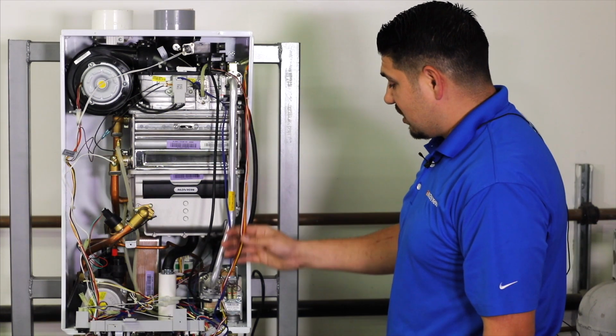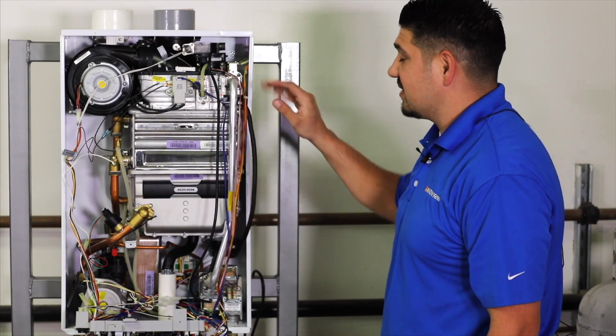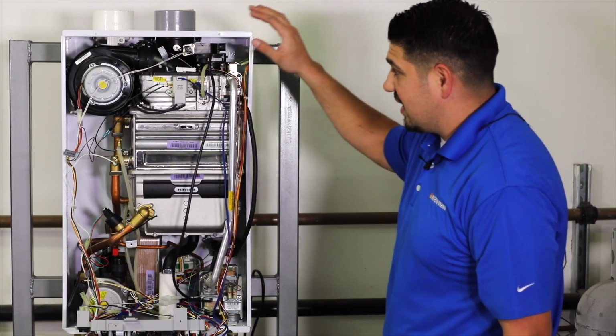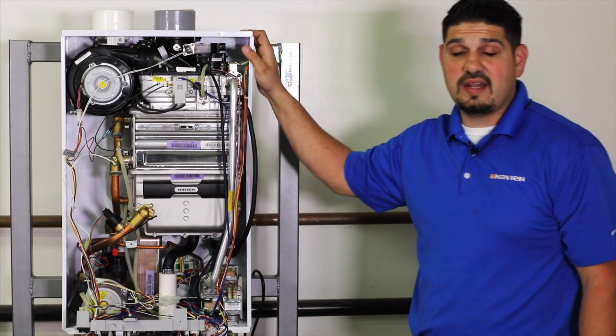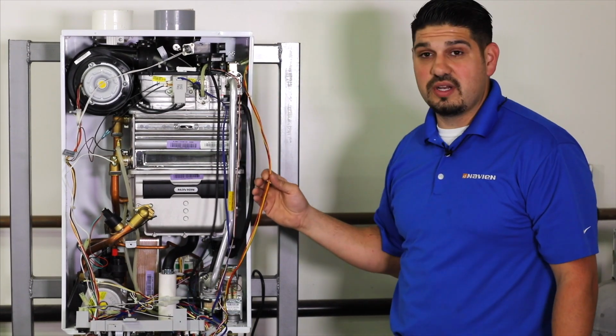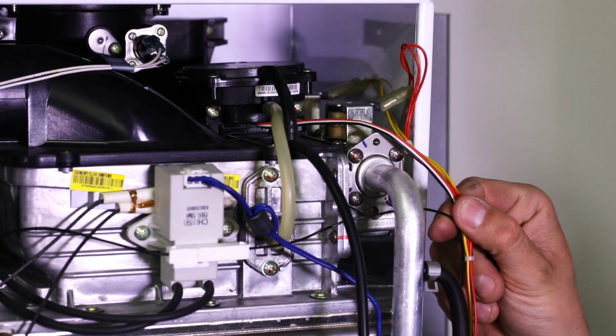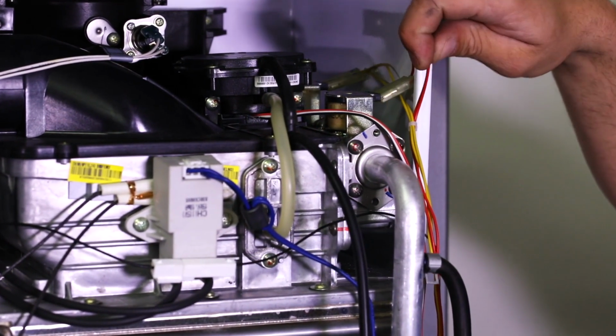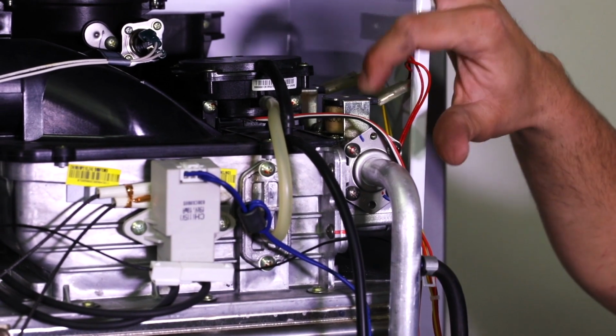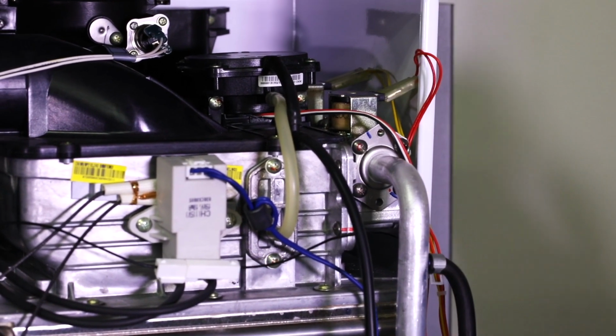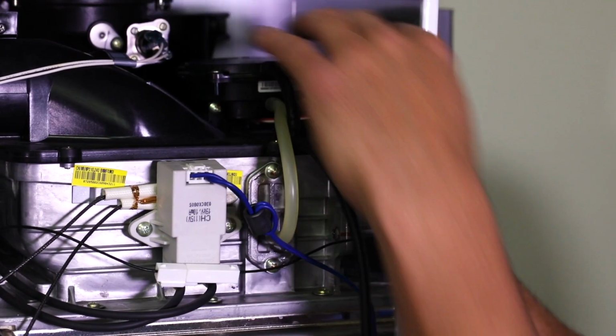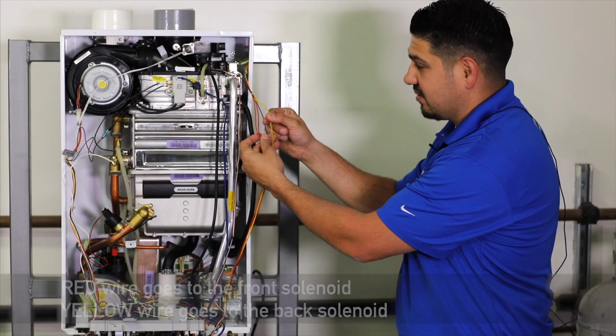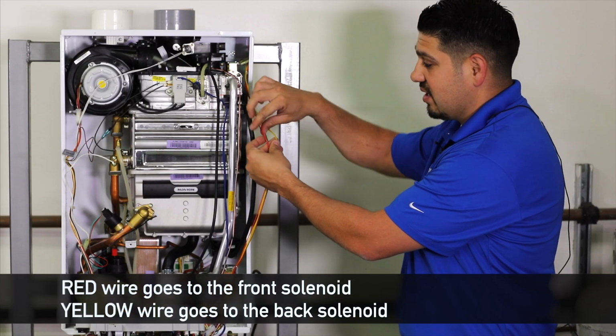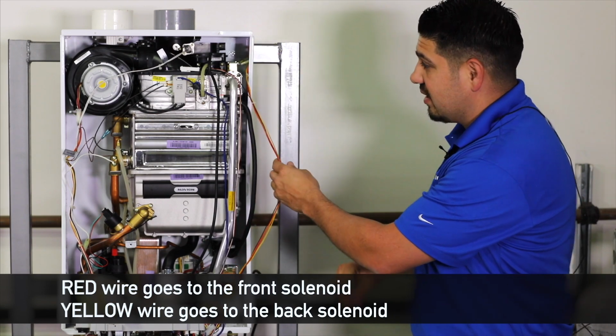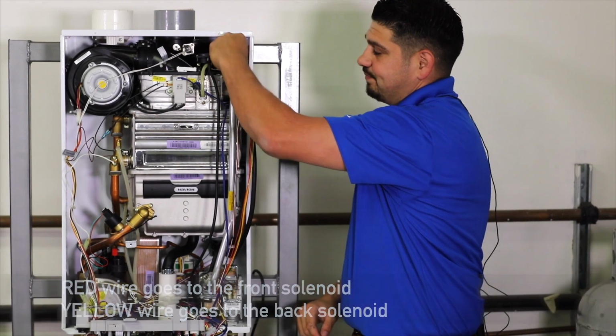What we're going to do is go ahead and follow these up and disconnect everything that they're connected to. Now, this would be a good time to go ahead and label each one of these, because we're going to be connecting them later. And something that's really important to remember is on these 2 solenoid valves, you can mismatch or crisscross the wires, which can create a big problem for you down the line. So these 2 yellow or mustard colored wires go to the back solenoid. These 2 red ones go to the front solenoid. So we're going to go ahead and unplug those now.